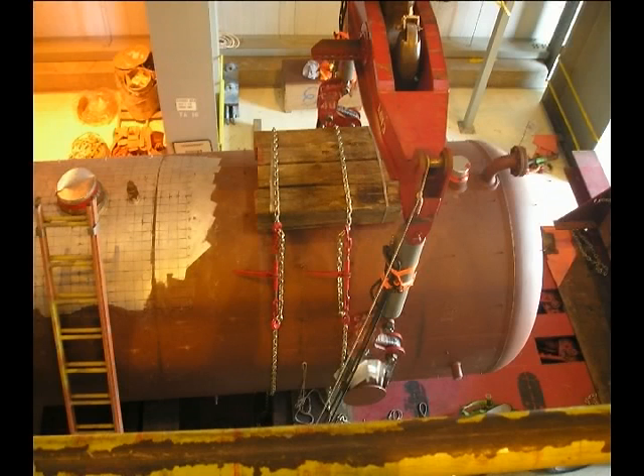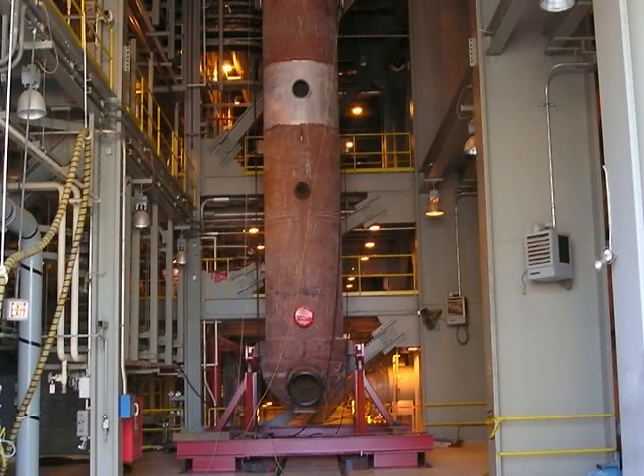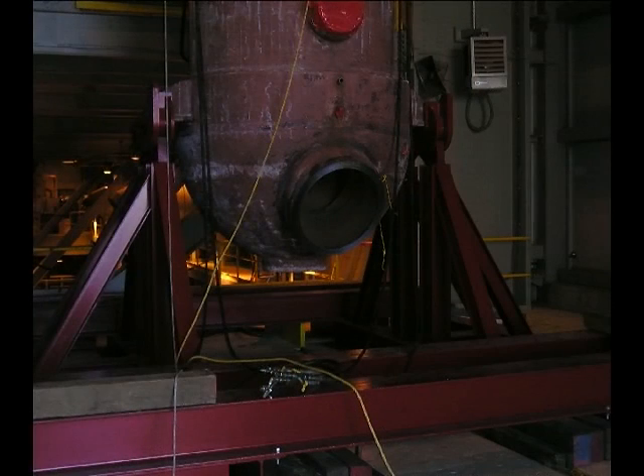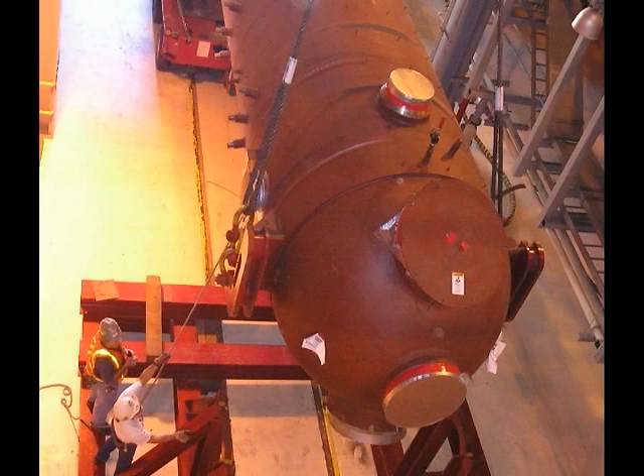At this point, the spreader bar with its lifting cylinders were removed from the main hoist. In order to lift the unit and reposition it so that the entire feedwater heater was supported by the Goldhofer trailer, the main crane hoist was re-rigged with lifting slings attached to the lifting trunnions and lift bracket. The overhead crane was now able to lift the vessel and traverse it into position on the platform trailer. The unit was then lowered onto staging beams that had been preset on the platform trailer deck. Upon securing the load, the self-propelled trailer transported the unit out of the turbine building and placed it on staging stands. It was now time to install the new feedwater heater, which would occur utilizing the same methodology, only in a reverse fashion.